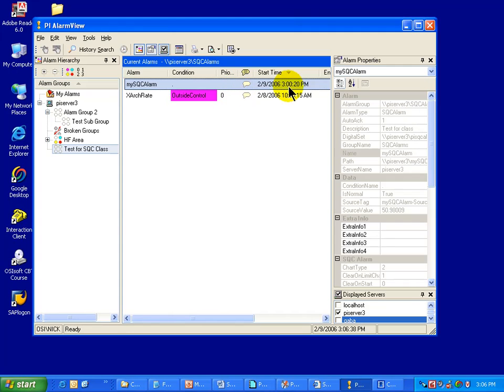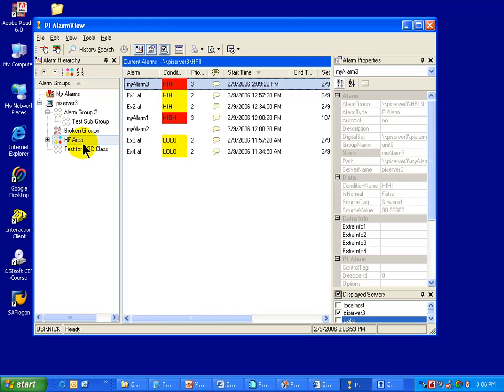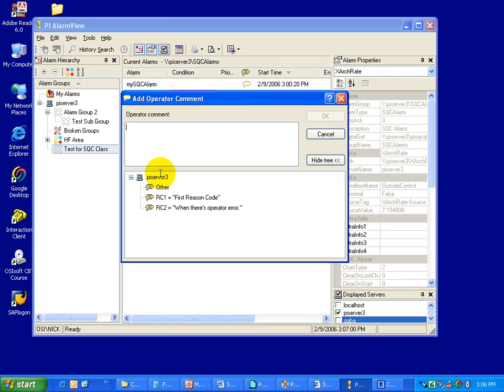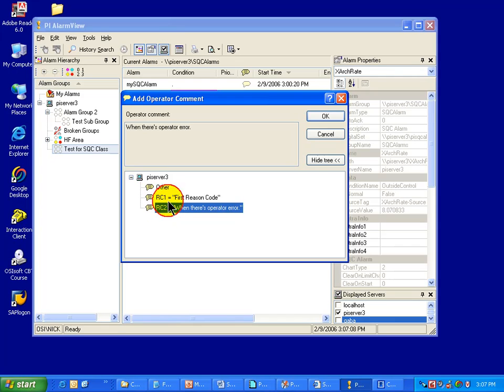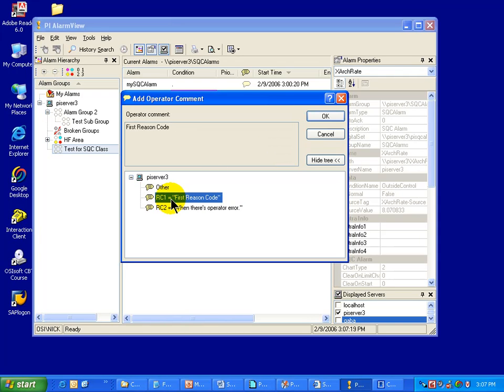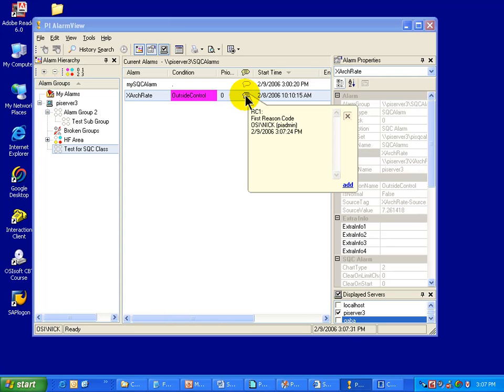When I do show an alarm, there's a whole set of information available just by looking at this panel. You can see the Alarm Condition and the Alarm Priority — right now this is a Priority of zero, while some other tags show Priority 3 or Priority 2. You can also specify that you'd like to make a comment by clicking on the alarm, where you can either type in a comment or specify a Reason Code retrieved from a Reason Code database that is part of Alarm View.